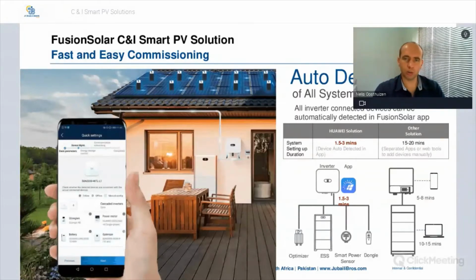So focusing on the auto detection of the Huawei inverters, or of the commissioning. Using the Huawei solution of auto detection, a system can be as quick as 1.5 to 3 minutes, where the competitor might be as long as 15 to 20 minutes. The system I've used here is a residential solution. It's got optimizers, your energy storage system, smart power sensor, and a dongle. It doesn't matter on the complexity or size of the system, it's as quick as 1.5 to 3 minutes. But on a competitor, it can take 5 to 8 minutes just on the inverter setup, and then an additional 10 to 15 minutes just for the setup of the energy storage system.